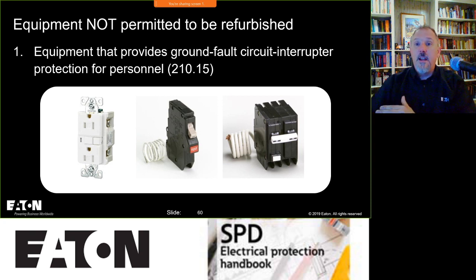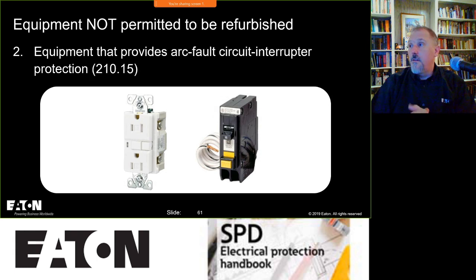I would say always be mindful if you're reusing - make sure you know the history of that product, because that breaker can look brand new because it was just washed after being in a flood. You don't know what's going on inside. If you don't know the history, if you're not getting an authentic product from a retailer or distributor that's qualified to handle those products from the manufacturers, then be very careful with that equipment, because you don't know the history.